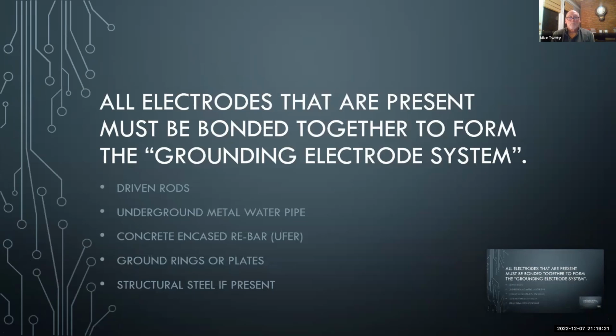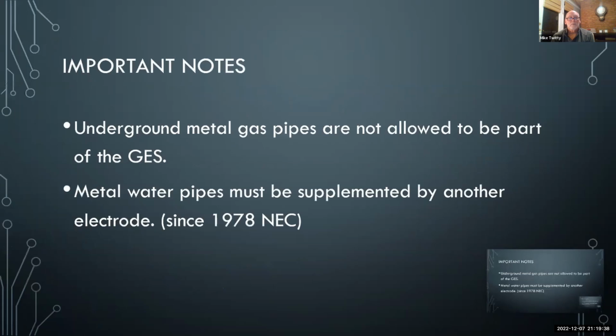Okay, all electrodes that are present must be bonded together to form the system. They can be driven rods, underground water pipe, concrete encased electrode, UFR, ground rings or plates, and structural steel if present. So let's talk about that a little bit. Underground metal gas pipes are not allowed to be part of the GES. They can be bonded and should be bonded, but they're not part of the grounding electrode system. Different situation. Bonding is different from them being part of the grounding electrode system.